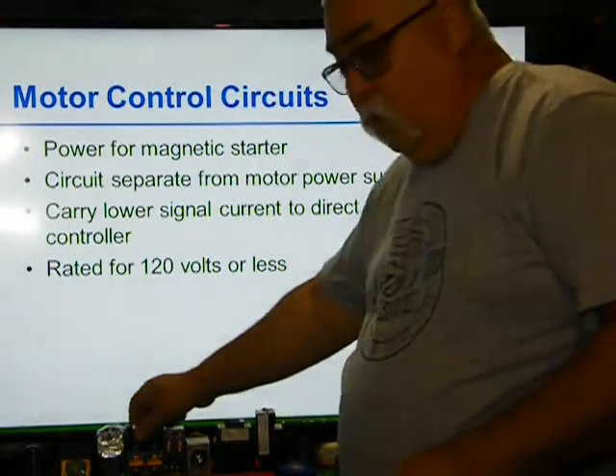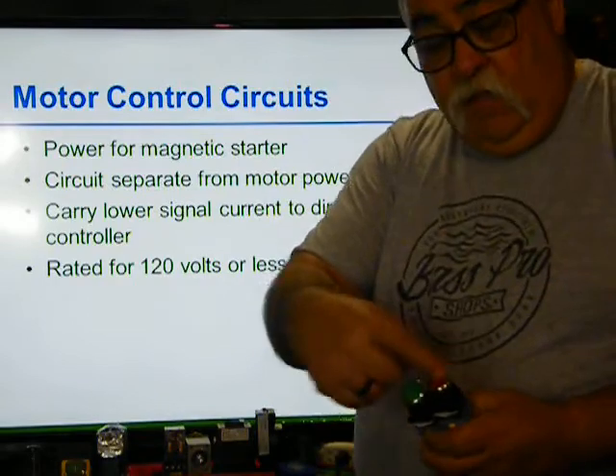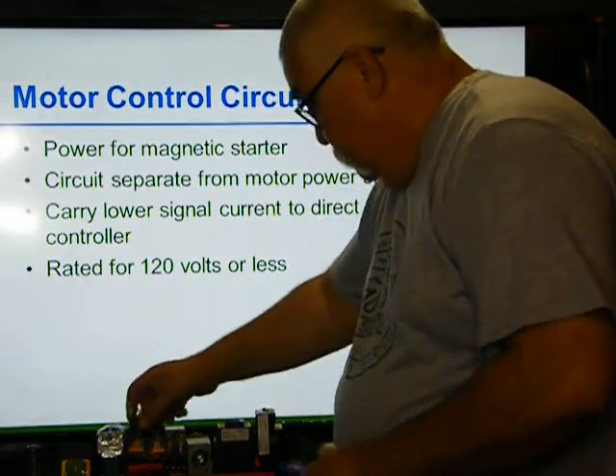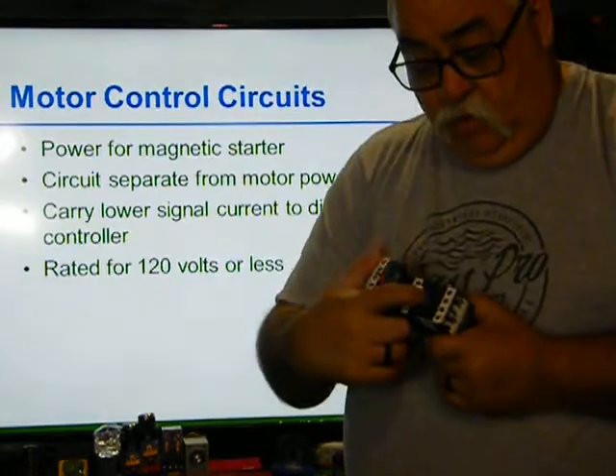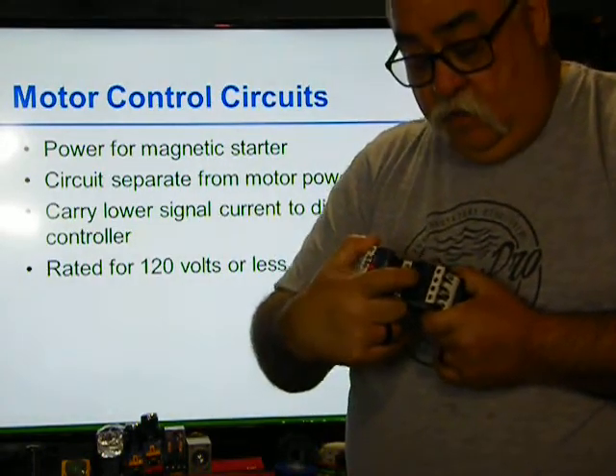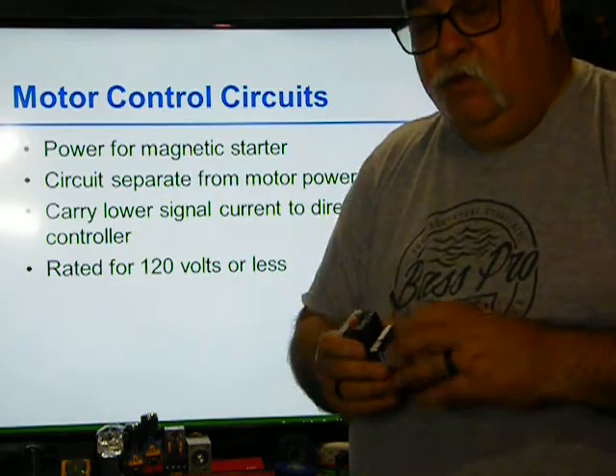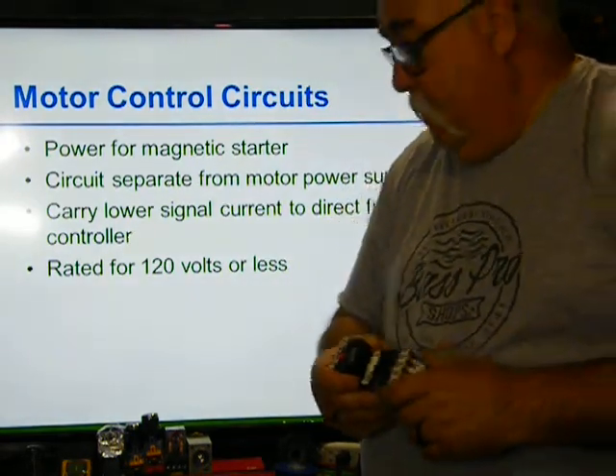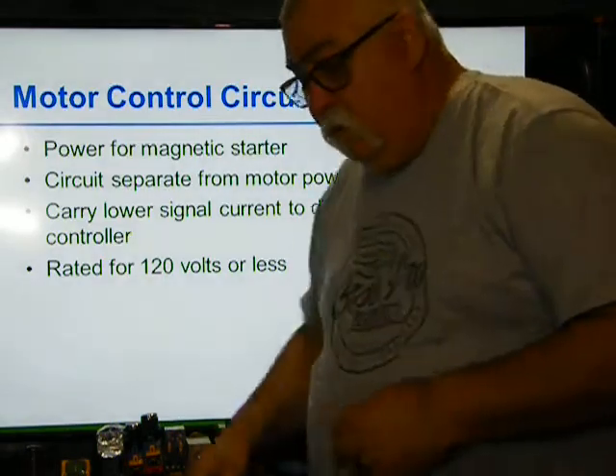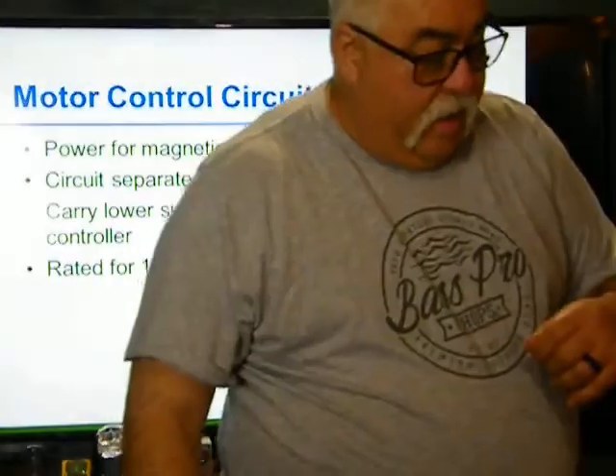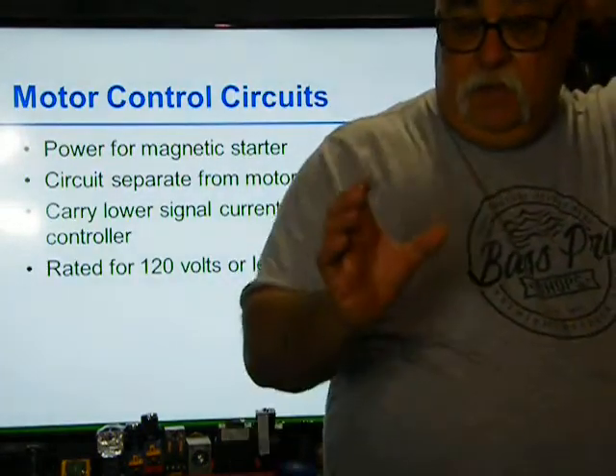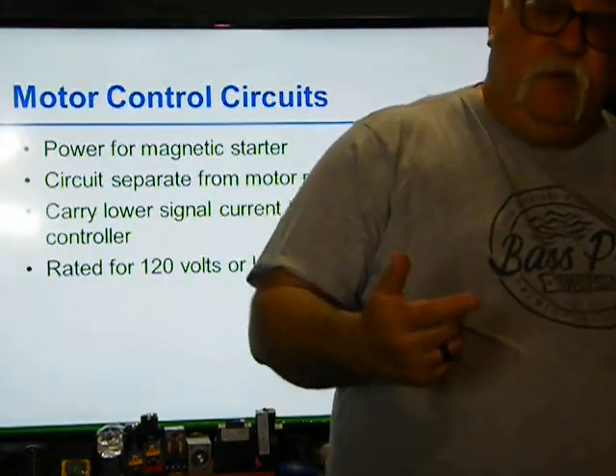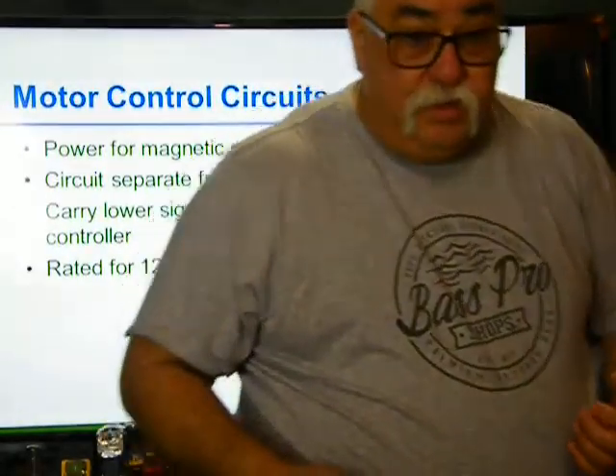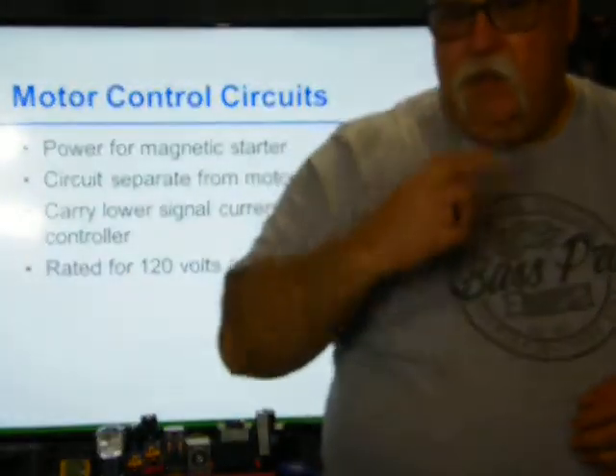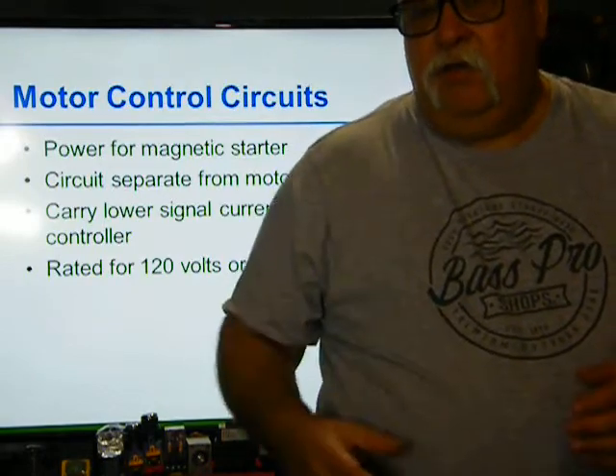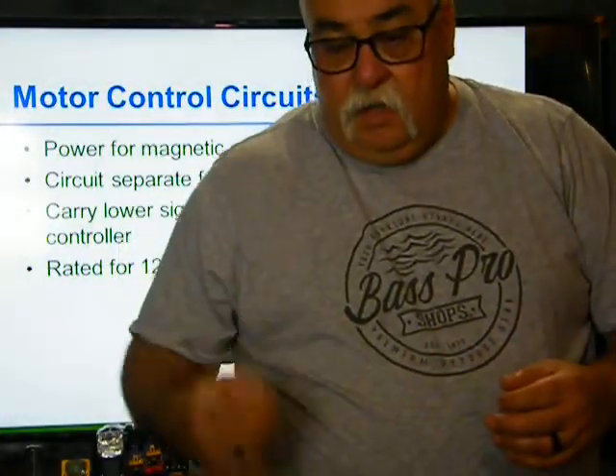That circuit is only doing whatever these lights use and whatever this coil uses. So that's the only power that's going to be there. There's no load; load-wise, this is it. Most transformers, when you have, let's say, 480 coming in and you're knocking the voltage down to 120 volts, you're going to have primary protection and secondary protection on the transformer. I have the ones in the classroom. I don't have one with me here, but you've seen those before. I passed them around when we did motor controls and electrician two.